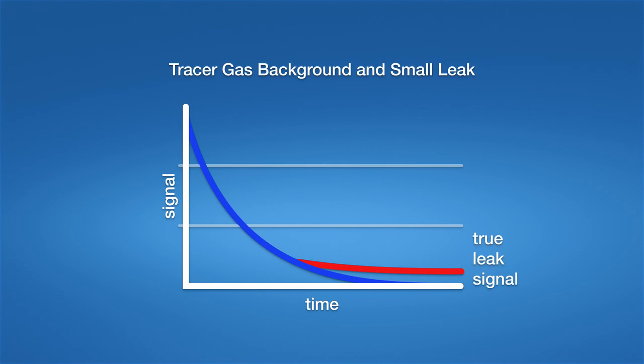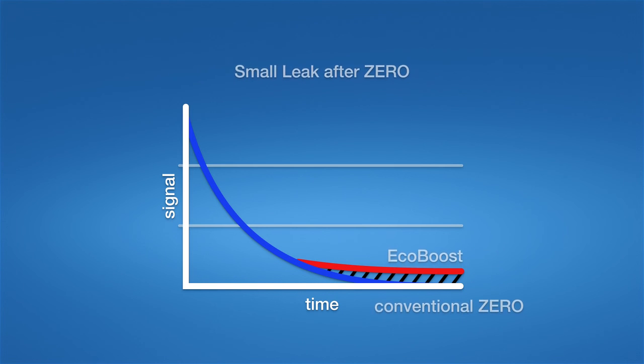All it needs to work correctly are two seconds of the decreasing blue curve. With a conventional zero function, you always need to wait a long time until the blue curve is stable enough to see small leaks.